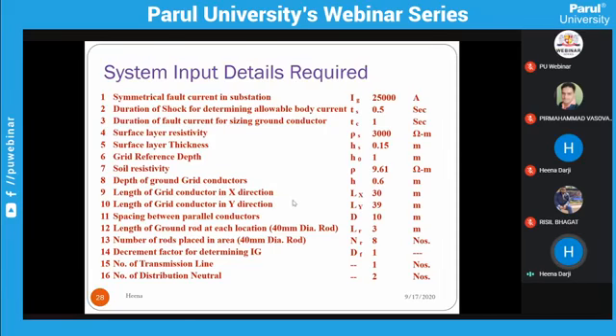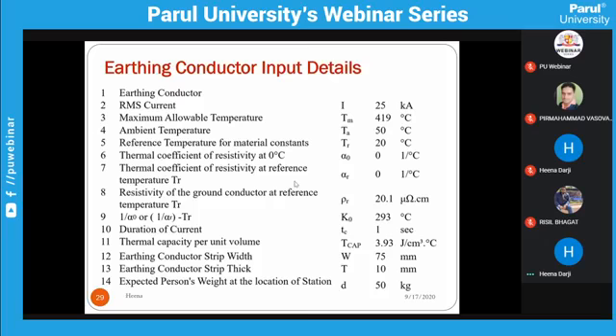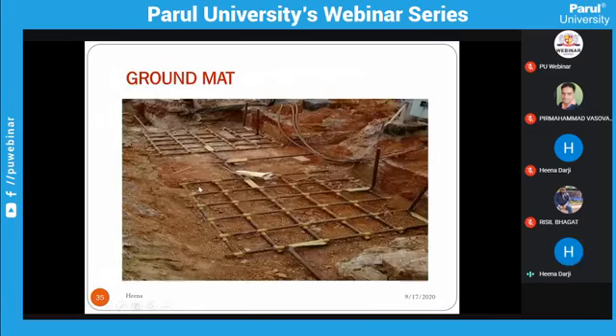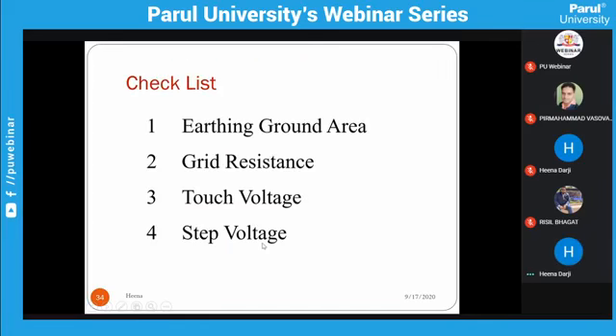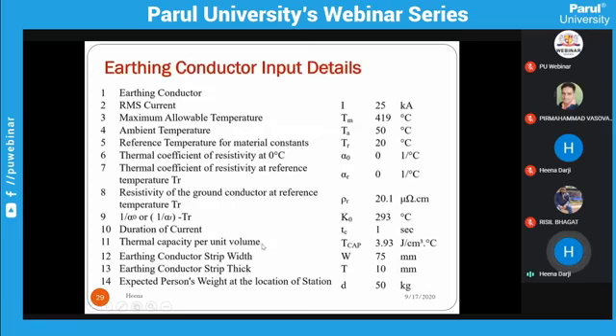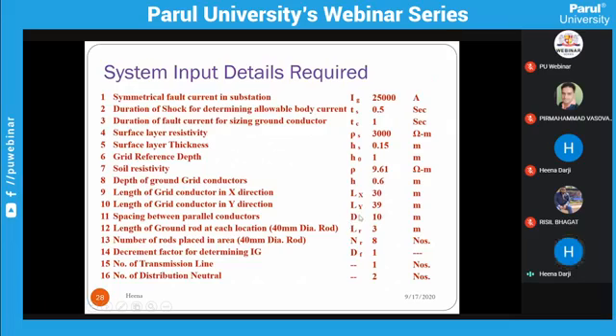Now, spacing between parallel conductors. I'll explain, just a minute. This is the earth mat, right? Your substation area, this direction is Y and this direction is X. So your spacing is from one conductor to another conductor, the same way this conductor to another conductor. This is your substation area, and your mat spreads like this, and the spacing between two conductors is this D, which is 10 meter. It depends on your design and experience.